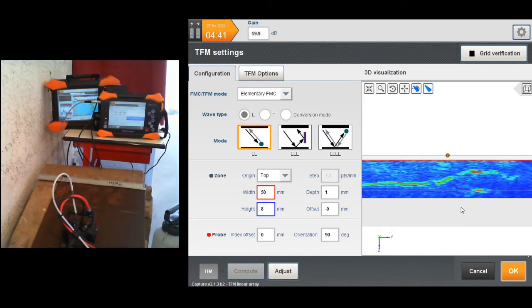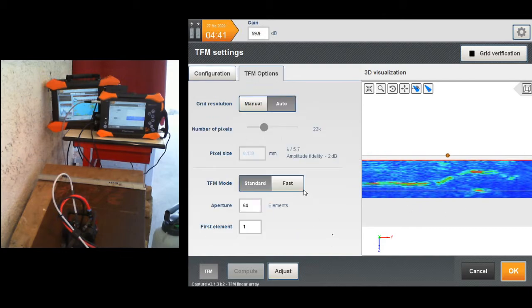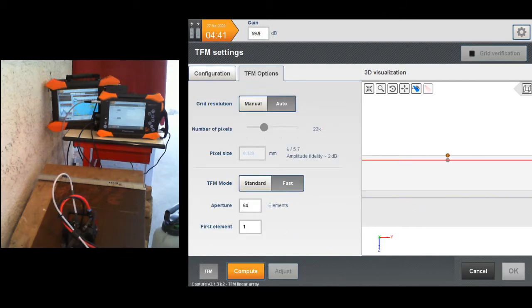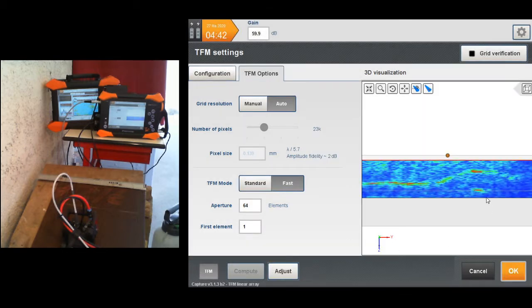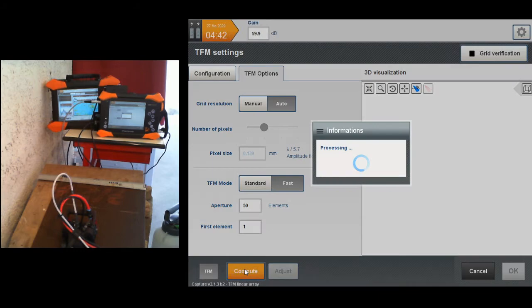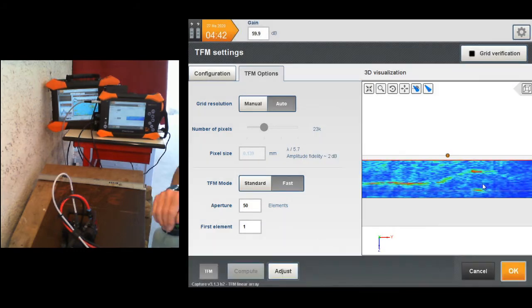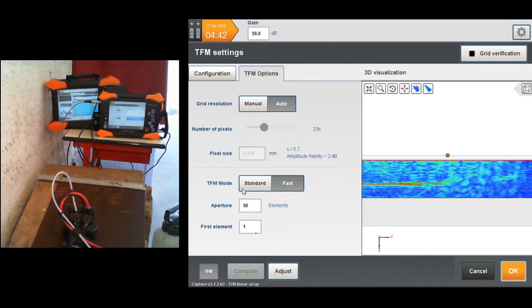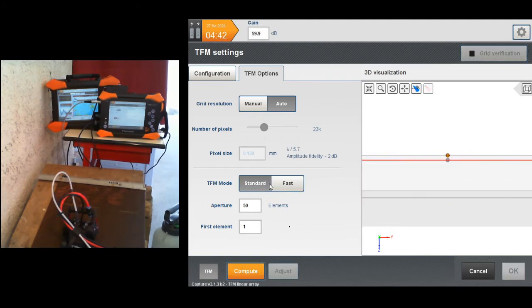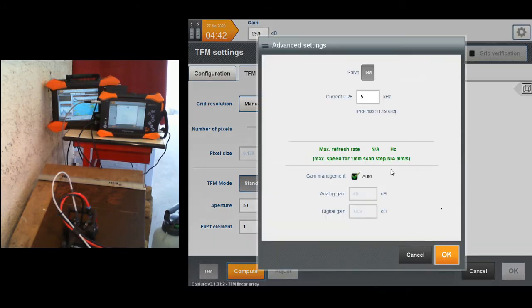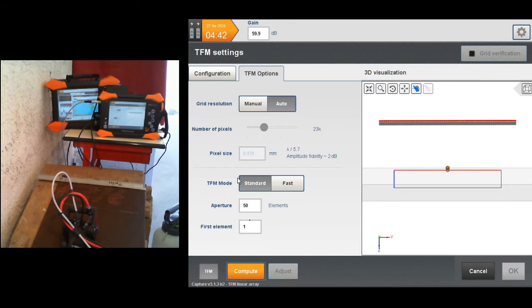And for sure, if you want to perform a scan which will be fast, you have some fast option here, but I think it will give you in this case a bit more noise, you see. So it's always a matter of compromise. You can change the number of elements if you want, so you really have access to different parameters. Okay, still. And in fact, fast will be 3-4 times faster because in fact the acquisition rate can be quite low, depending on the scanner I set up.